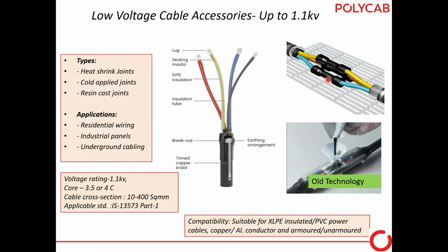In the same way for a joint, we prepare the cable, use ferrules, and connect the conductor through the ferrules. Over that we give heat shrink tubings, and over that armoring, we provide the canisters, and for outer protection we use a wraparound sleeve or outer sleeves. Generally, these LT cables come as 3.5 and 4 core systems, and cable accessories come for the same. But if a single core or 2 core is required, that also we can provide.